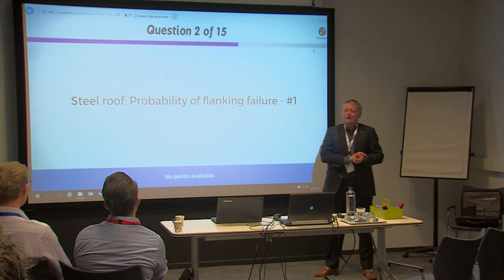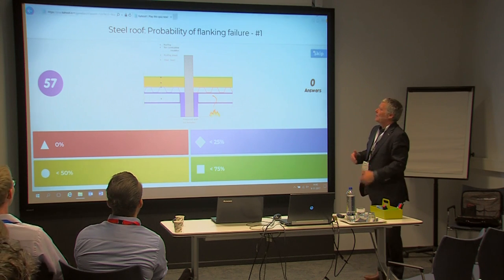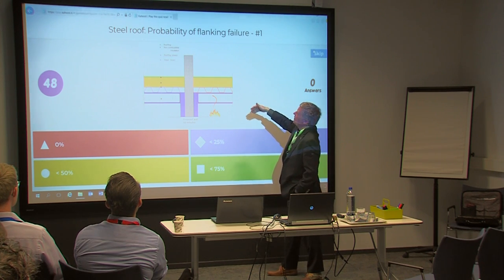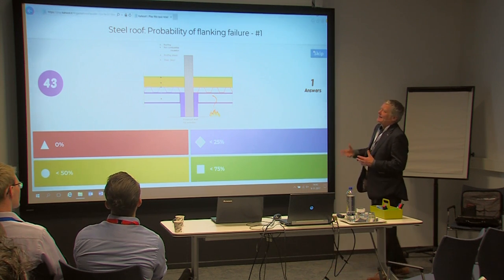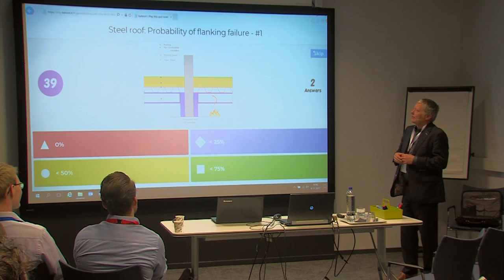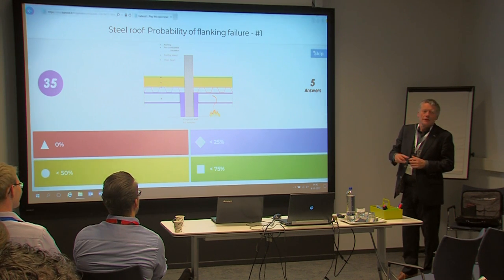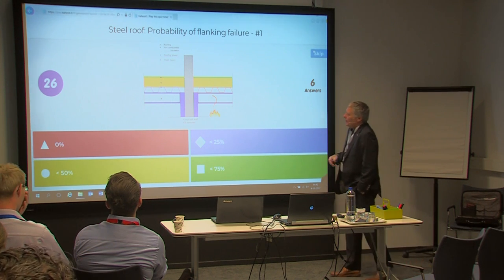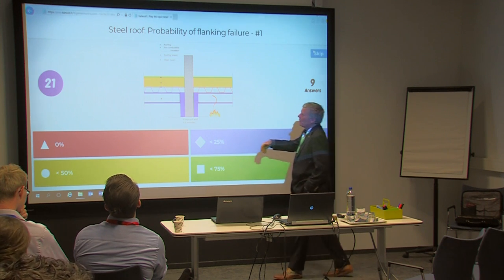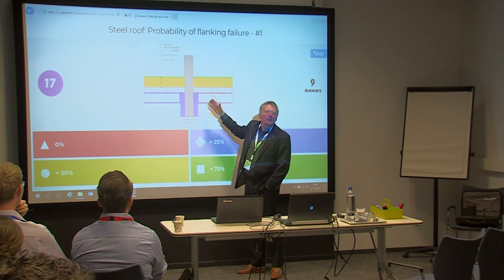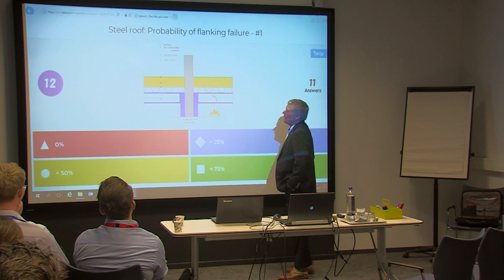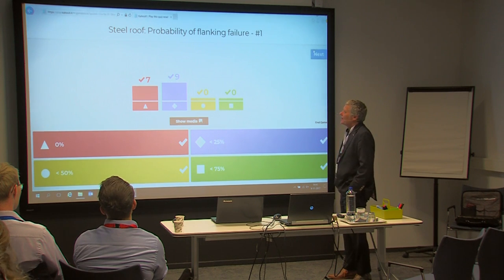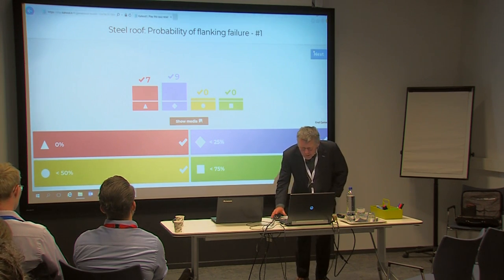First detail — a steel roof: what is the probability of flanking failure? It's only about flanking, not the direct path. This detail has a non-combustible insulation roofing with the compartment wall acting as a barrier. Failure probability means the probability of not meeting the criteria for a fire-safe construction — too much energy flowing through via the flanking path. The options are: zero, 0–25%, 25–50%, or 50–75%.